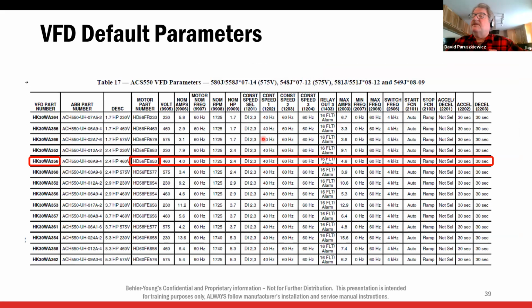So I want to look at this for a second here. We find the drive, we find the blower. And if you look down this list here, this is all pretty common sense. 460, so if it's a 460 volt unit, set it. Nominal amps, 4. Motor hertz, 60. RPM is pretty self-explanatory, nominal horsepower. Now, this nominal horsepower, the motor, this is nominal, it's not horsepower. They're 2 different ratings.